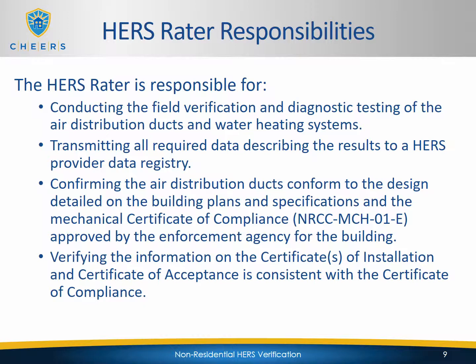As the HERS Rater, you will conduct field verification and diagnostic testing of air distribution ducts and/or water heating systems, transmitting all required data to a HERS provider data registry, confirming that air distribution ducts conform to the design detailed on the building plans and the mechanical certificate of compliance approved by the enforcement agency. You will also verify that information on the certificates of installation and certificate of acceptance is consistent with the certificate of compliance.